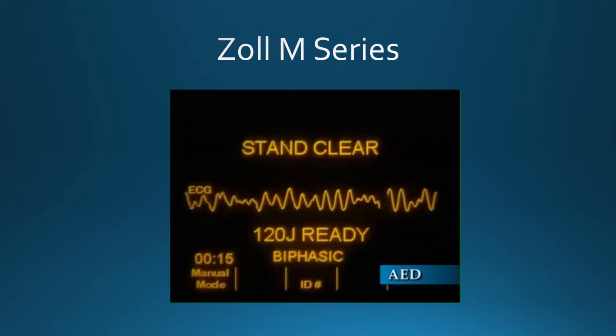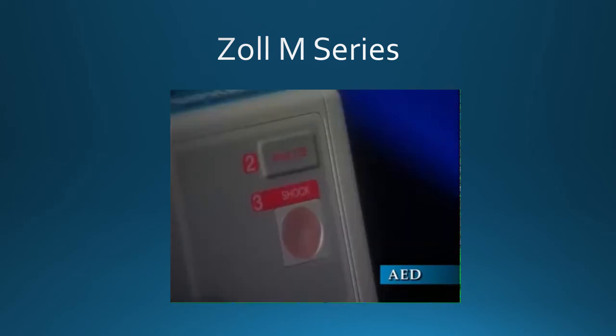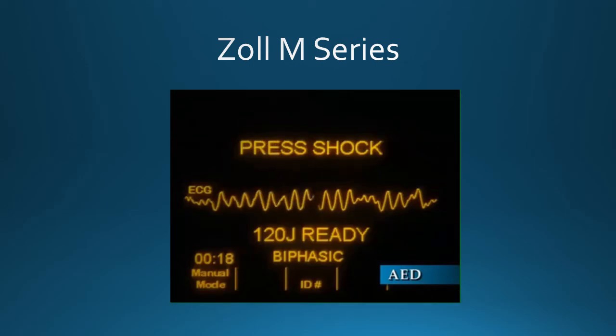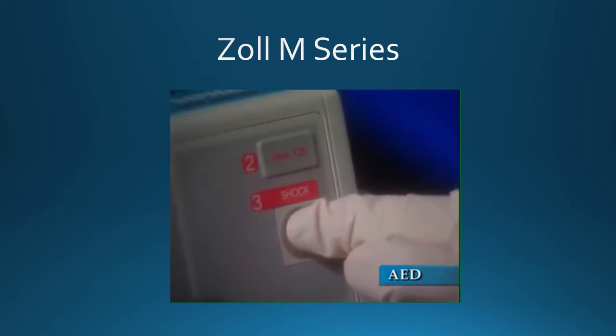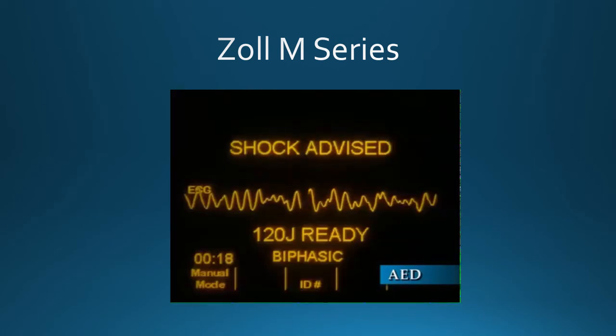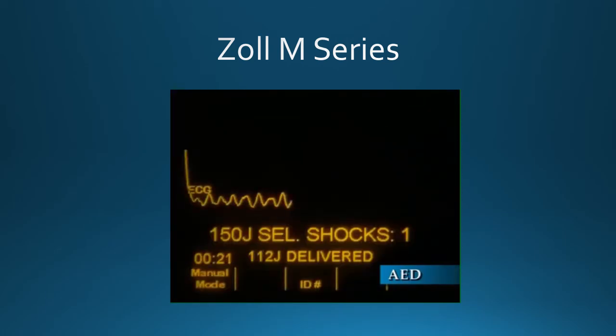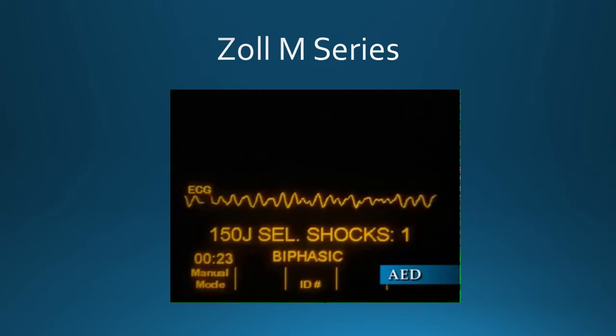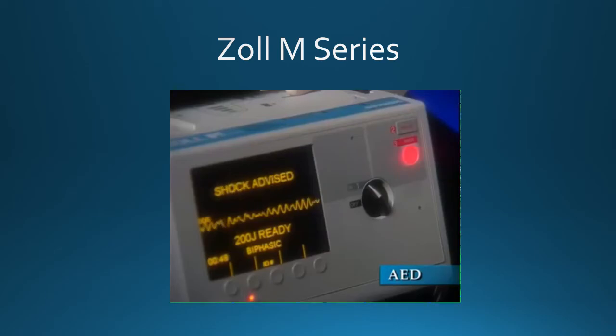Press shock. When the unit is charged and ready, the shock button will illuminate and the Press Shock message and voice prompt will be issued. Press and hold the shock button on the front panel until the energy is delivered to the patient. Observe the patient or the ECG response to make certain the shock has been delivered. A continuous tone will sound for 10 seconds, followed by an intermittent beeping for 5 seconds. The shock must be delivered within this 15-second interval, or the defibrillator will disarm itself.